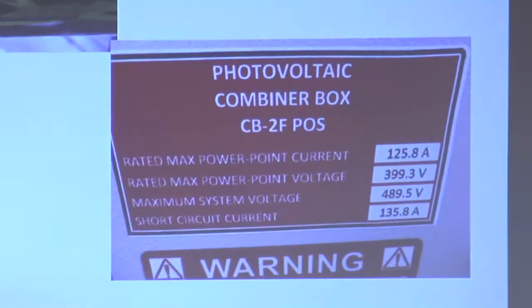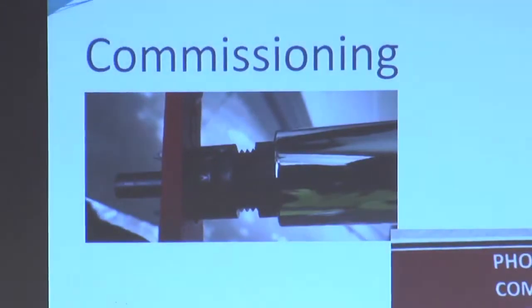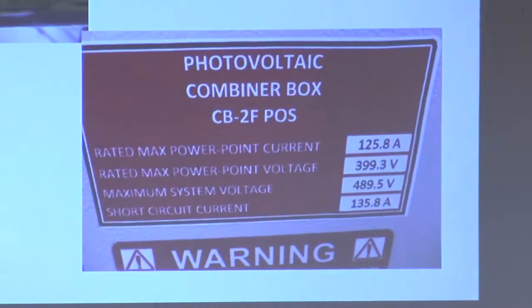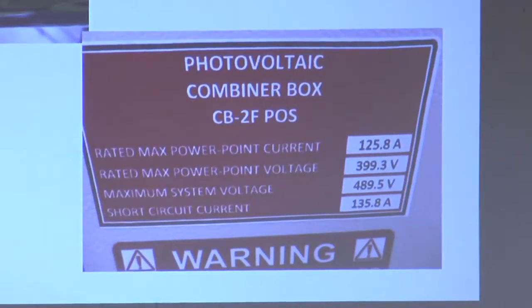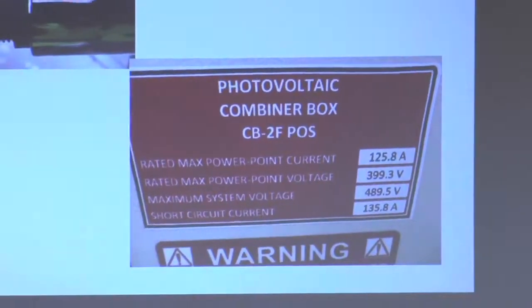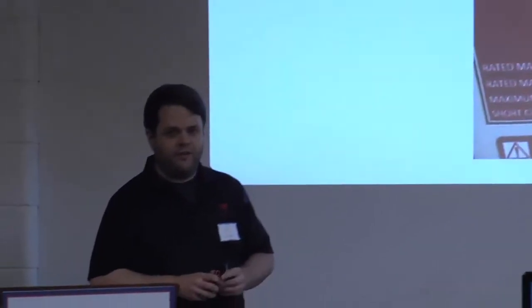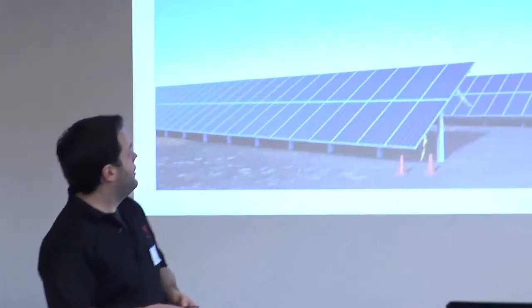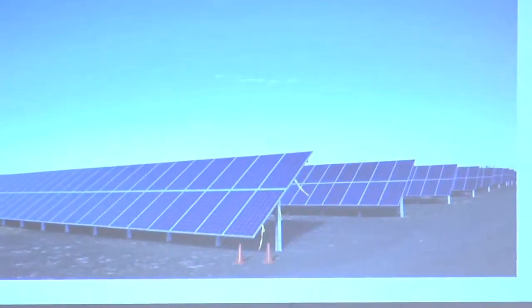So part of that included very simple tests like torque testing the MC4 connectors between the modules, and part of it was doing IV curve testing on the strings themselves. So we would go open the combiner box, put our testers on the positive and negative bus bars of the combiner box, and basically open each string one by one and check for proper voltage and current. And there's a quick picture of the finished array.